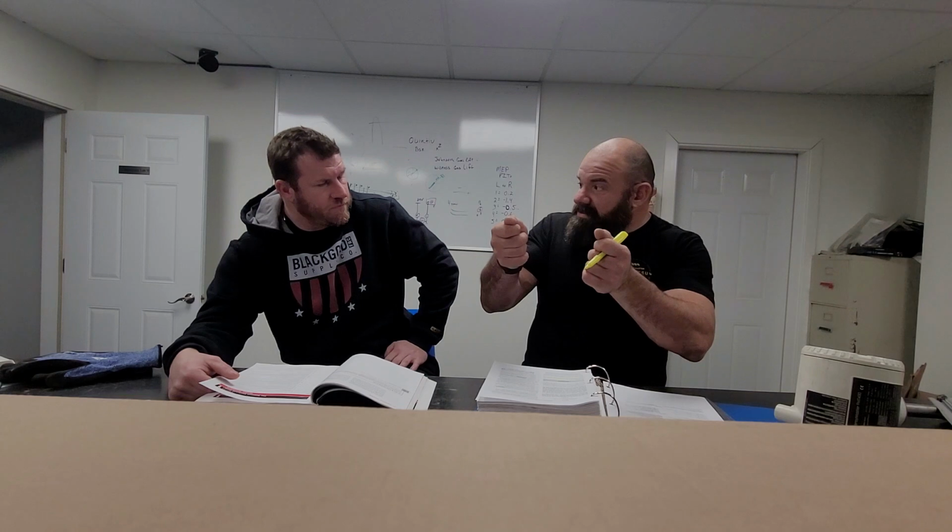How about most voltages referenced in the NEC are blank voltages? They're nominal voltages. So what we mean by that is when you're testing a 120/240 volt system, you're going to see 119, 239, something like that. Right. They're nominal voltages, so it's not referring to the actual voltage. It's the nominal voltage of that system. Right. And that's the way we talk about systems in terms of nominal voltages.